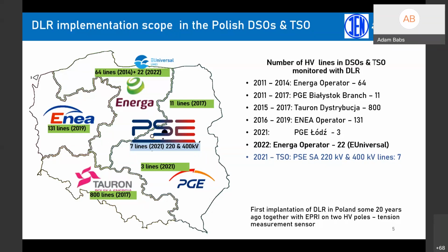So this is pretty enough, and for the time being, this critical line, critical span, which are selected for the supervision, are monitored. Within the scope of the EUniversal project, 22 lines are specified, located in the vicinity of the production of wind farms, which can be a bottleneck with leading out the power from the wind farm. These 22 lines, their capacity will be forecasted, taken into calculation of the power flow, and finally it will be assessed whether additional power can be generated by the wind farm or not.